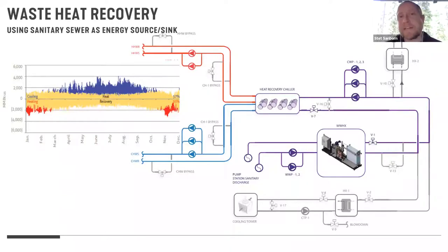So here's a layout of that system. As you can see, it provides hydronic heating and cooling through a heat recovery chiller, or heat recovery heat pump, I think would be a little more accurate. Then on the source side, when we're out of balance and don't have simultaneous heat, it's looking for a source, and that source is a heat exchanger going towards the sanitary pump inlet and outlet. So we're stealing sewer water and then pumping it back in. This has a really nice benefit because of the consistency of that temperature. We can design around it. It's a really finite window of source energy. And ironically, because that sewer water is typically closely associated with ground temperature, we don't see a huge fluctuation throughout the year.